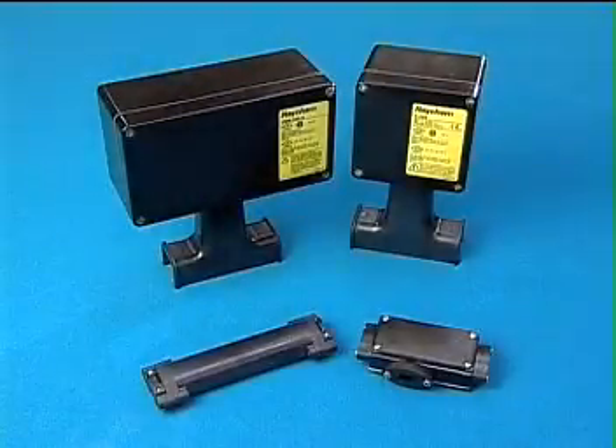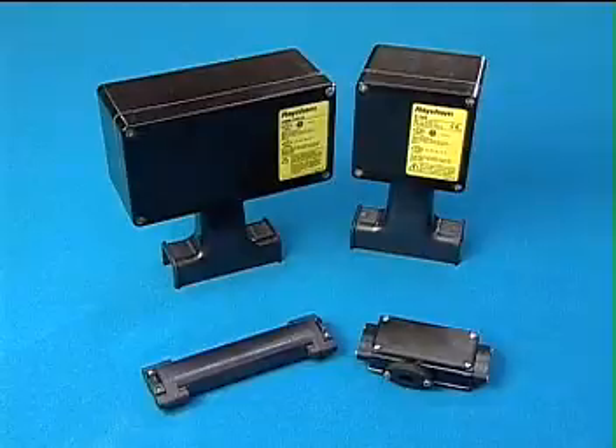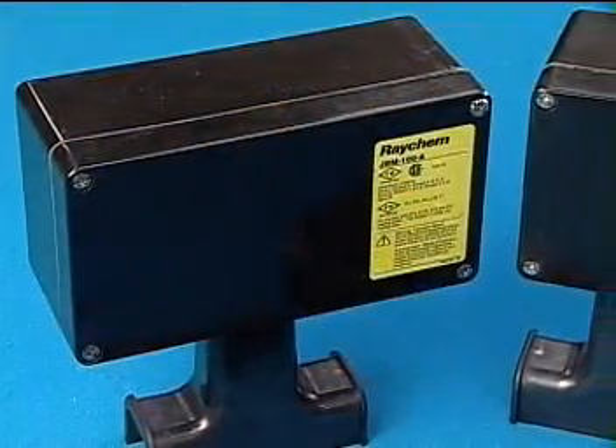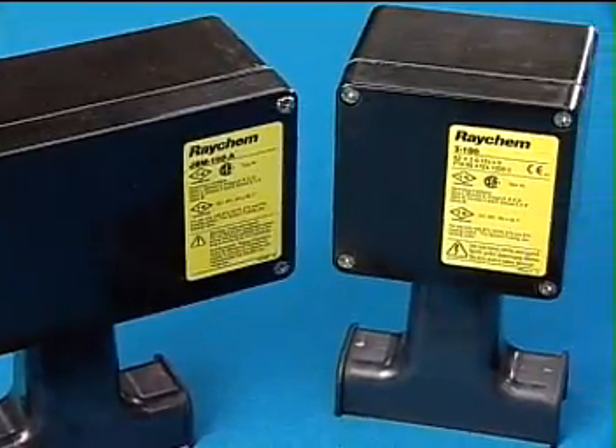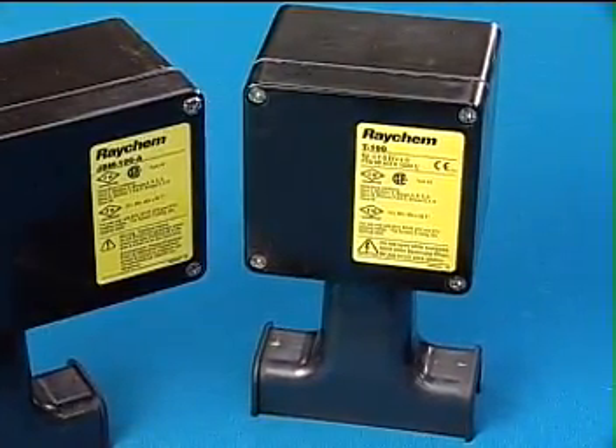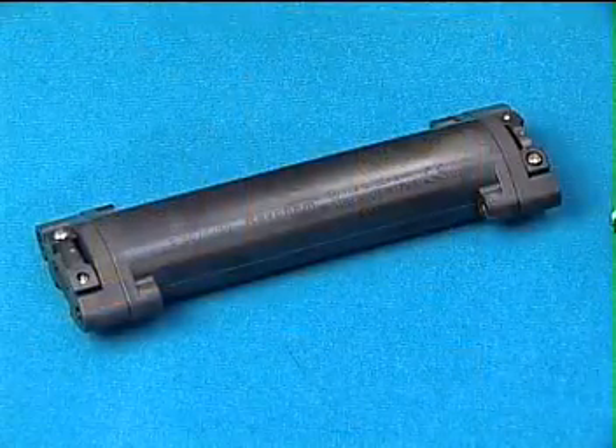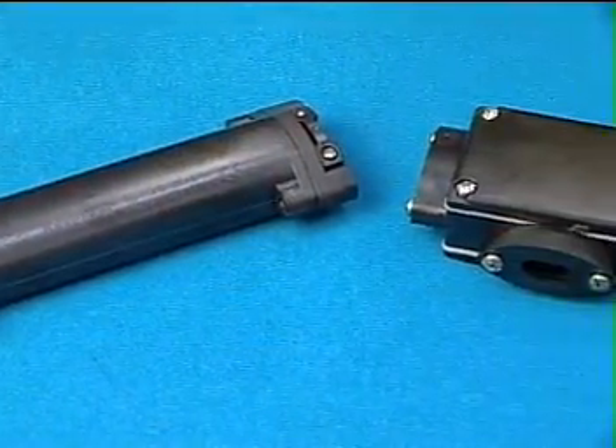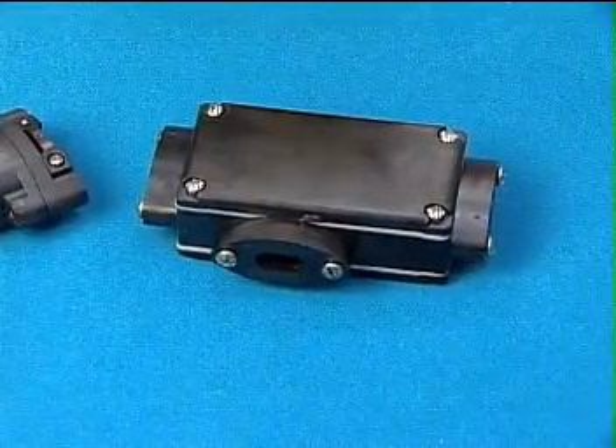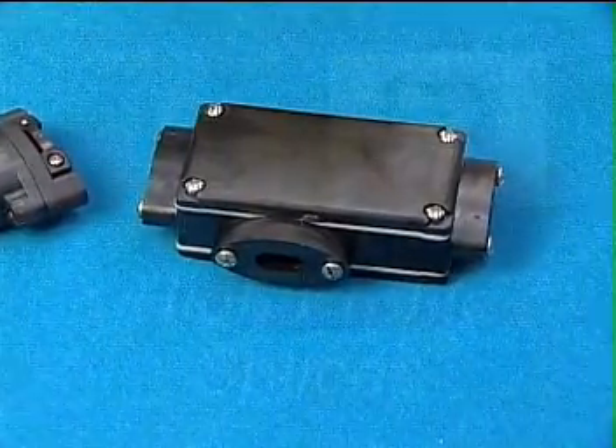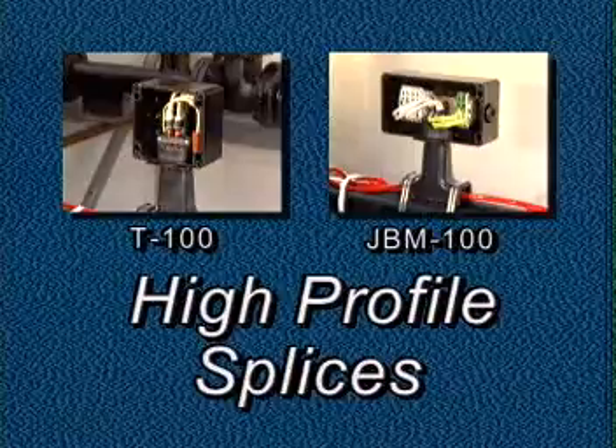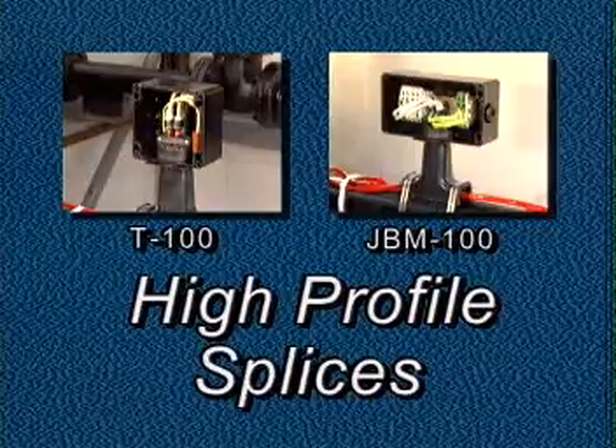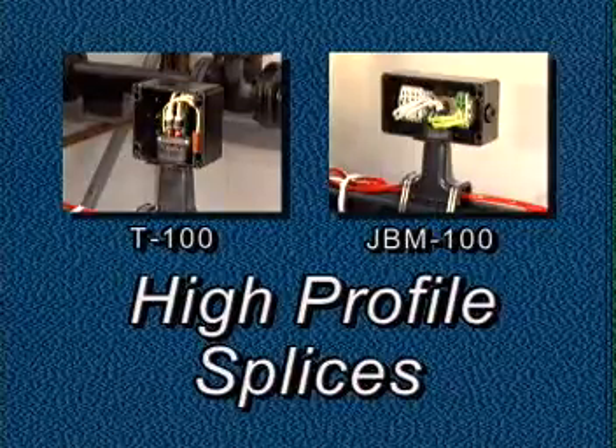There are 2 types of kits available for making tees or splices, both above and below the insulation. The JBM 100, which uses terminal blocks, and the T100 that uses crimps, are both installed above the insulation. The S150 is used for splices below the insulation, and the PMK GLT for tees below the insulation. Use the same heating cable prep technique for the T100 and the JBM 100. Refer to the installation instructions for specific details.